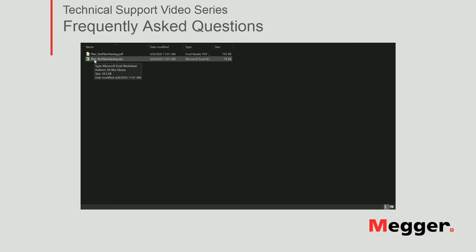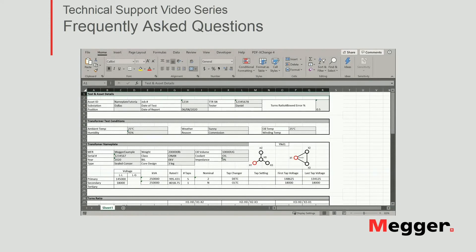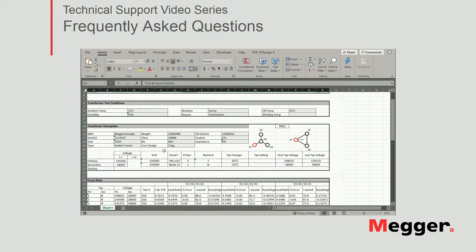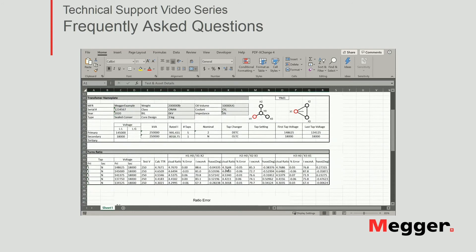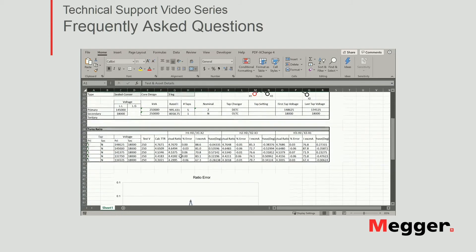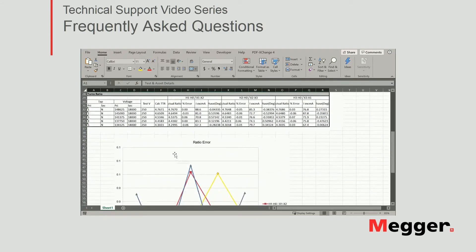We also get two files: an Excel and a PDF. Let's open the Excel first. My report in Excel format is now open and you can see it includes all the details that we included in the test plan — the test conditions, the transformer nameplate, as well as every piece of information that was gathered during the test itself. Scrolling down, you'll see all your turns ratio results, all measurements, all three phases, all five tabs, as well as a graph.